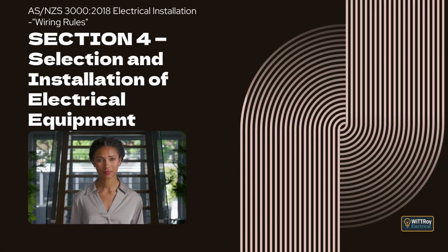Clause 4.10.6, Signs. This clause explains that where heating cables are installed, suitable signs must be provided at each location to draw attention to their presence. It explains that where there is a risk of overheating due to coverings or building materials placed over embedded heating equipment, warning signs must be provided. It explains that this requirement can be met by clearly and permanently marking the functional switch or switches for the heated area, or by providing suitable labeling at the relevant distribution board.